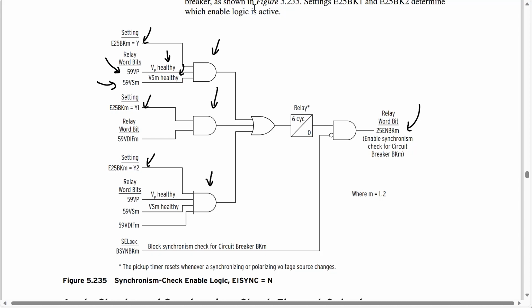Now, if you set the enable to Y1, so this second AND gate that we have over here, what that means is that the relay is only looking at the difference between the line side and the bus side voltages and making sure that that difference is not greater than a certain threshold. So you can see over here that we have a different word bit, 59V-diff1. That's going to be the difference between the bus side and the line side voltages. So in this case, the relay only looks at the difference between the two, but it doesn't check to make sure that it's within a certain window. So for example, if both voltages were at 50% of nominal, then this would be a logical one at the output of this AND gate, and the sync check element will be enabled, even though the voltages are well below nominal voltage.